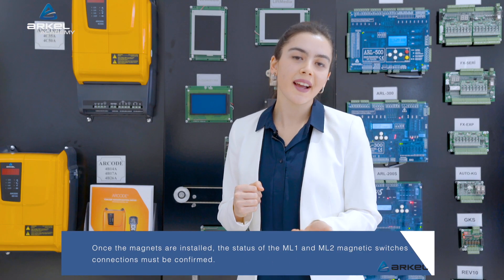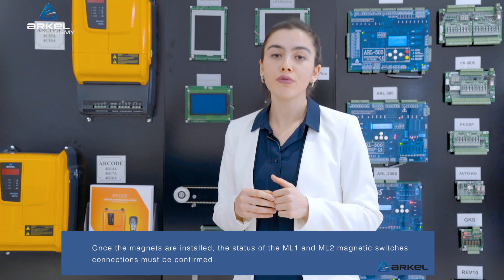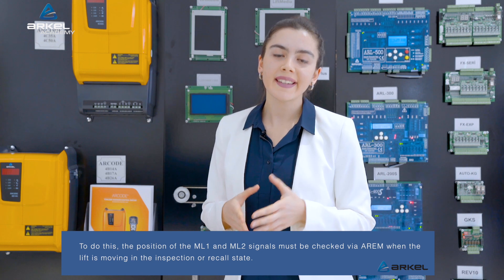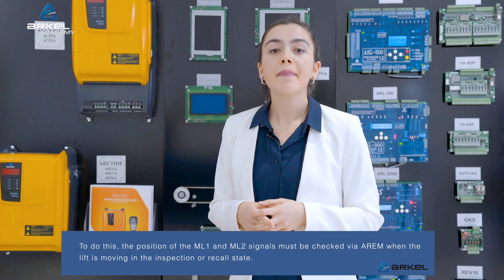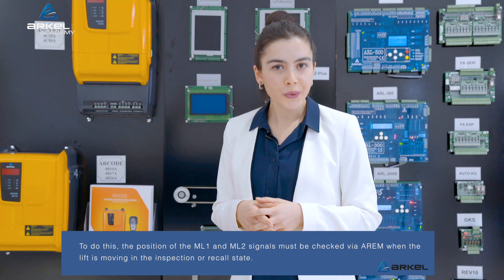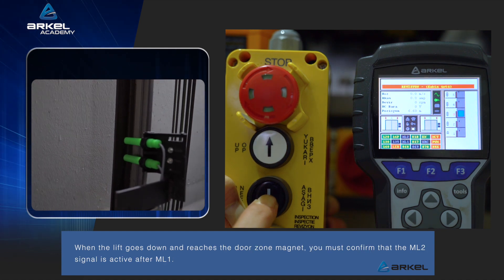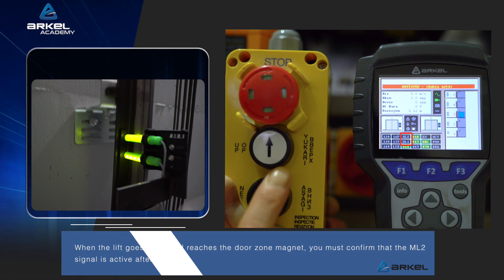Once the magnets are installed, the status of the ML1 and ML2 magnetic switch connections must be confirmed. To do this, the position of the ML1 and ML2 signals must be checked via AREM when the lift is moving in the inspection or recall state. When the lift goes down and reaches the door zone magnet, you must confirm that the ML2 signal is active after ML1.